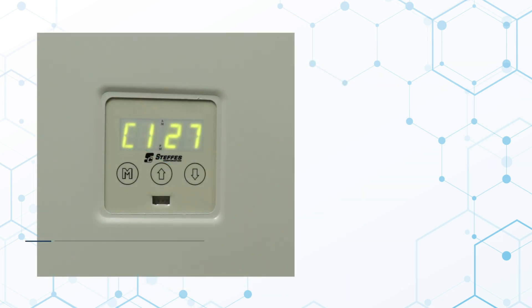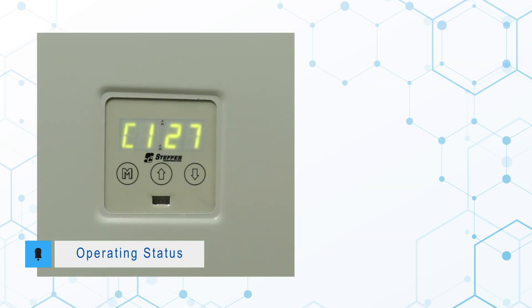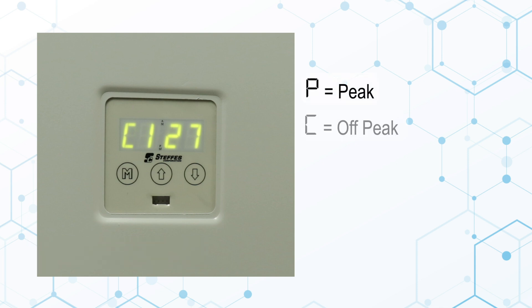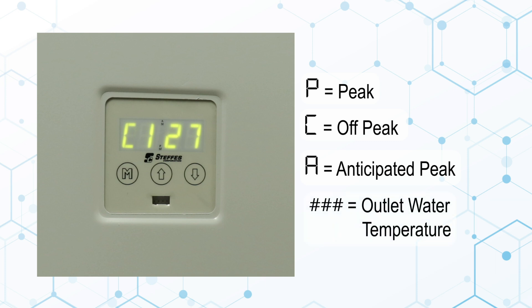The normal operating display on a residential hydronic system will show the current peak mode status. P indicates the system is in a peak period, C indicates a charge period, and an A indicates an anticipated peak period, if applicable. The number shown next to the peak status indicates the current outlet water temperature.